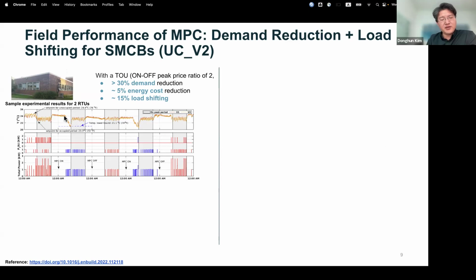Before this happens, model predictive control tries to pre-cool the space within the comfort bound specified by the user. You can see the pre-cooling effort in order to store energy using the thermal mass of the building, and then reduce the peak or the energy consumed during the on-peak price period.